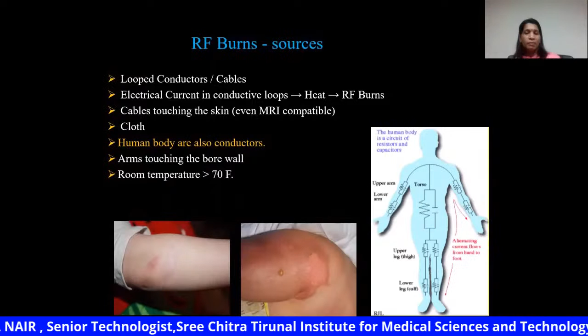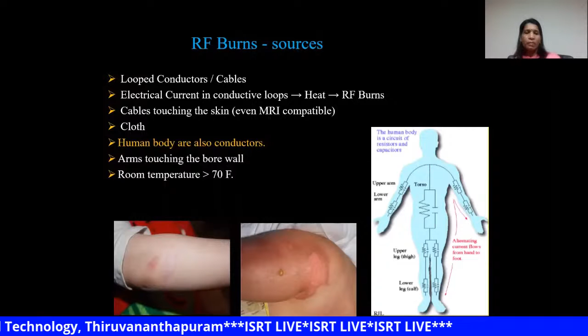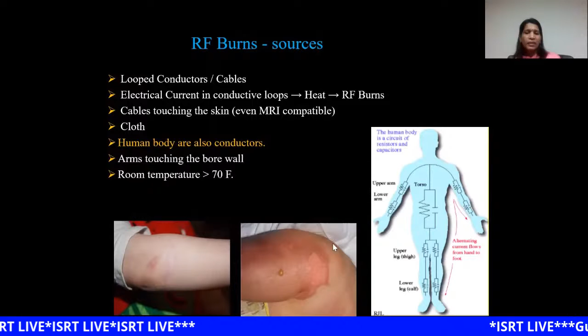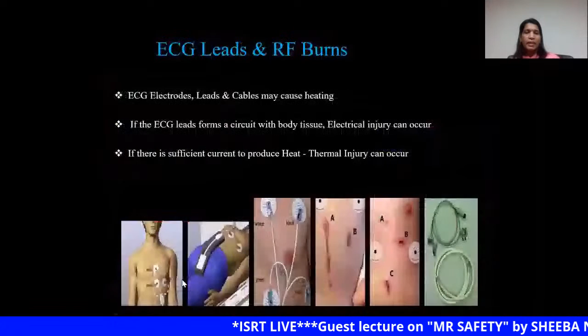In such a situation, a large current will be produced, and there can be a chance for RF burns. Also, avoid the patient's arms touching the bore wall, and always keep the room temperature less than 70 degrees Fahrenheit. So here you can see the RF burns that have occurred inside an MRI.